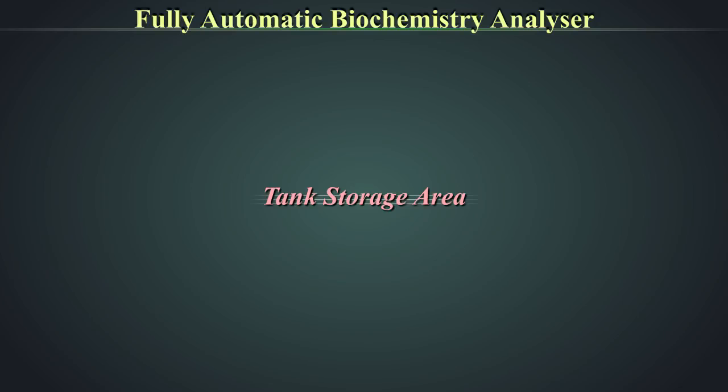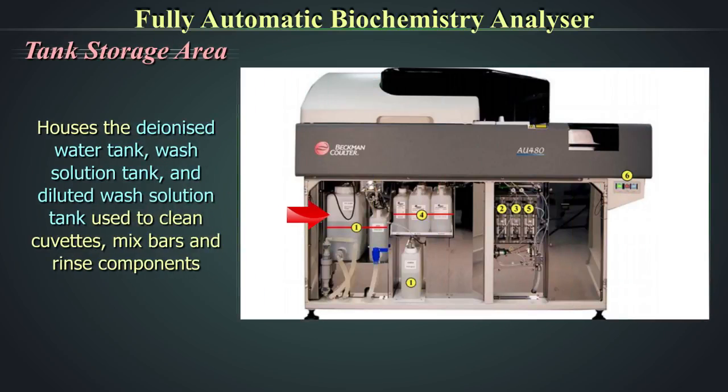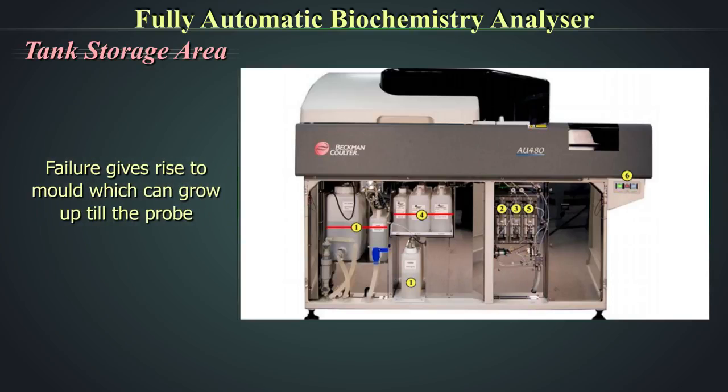Tank storage area. The tank storage area houses the deionized water tank, wash solution tank, and diluted wash solution tank used to clean cuvettes, mix bars, and the rinse components. Regular cleaning of this water tank and filters is very important. Failure to do so may give rise to mold, which in turn can grow up to the probes. For details on the cleaning process, get in touch with your service engineer.